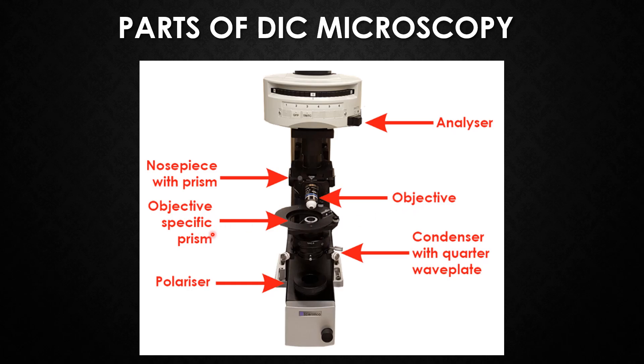The next part is the objective prism, or objective-specific prism. Either adjustable or filter-mounted, this upper prism recombines the separated beams into elliptically polarized light. Like the lower prism, this prism is formed by affixing two optical quartz wedges together. The wedges are cut differently so that one has its optical axis parallel to the prism surface, and the other has its optical axis at an angle to the prism's flat surface.